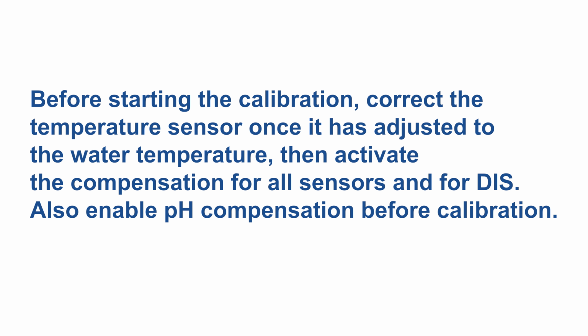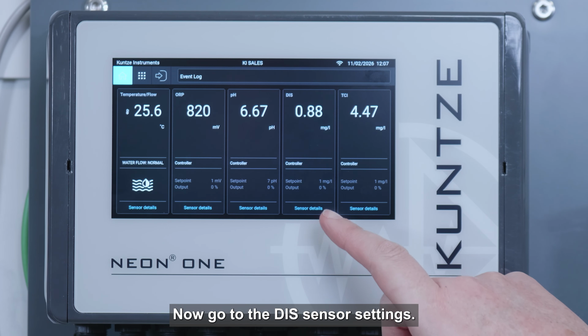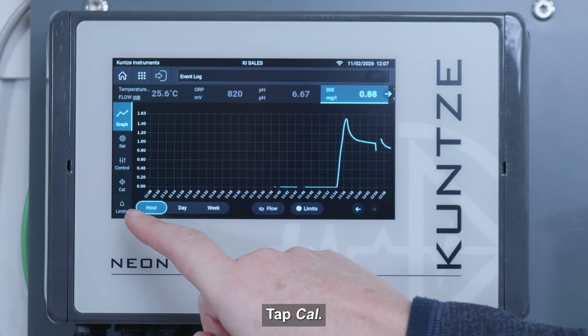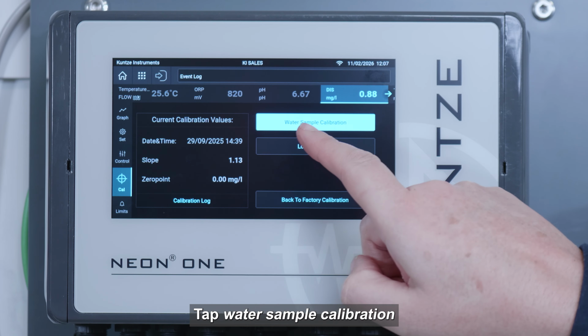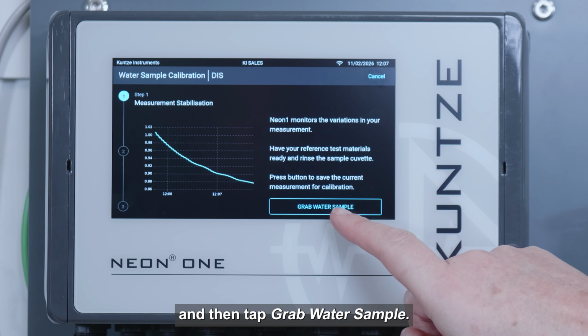minutes. DIS sensor calibration. Before starting the calibration, correct the temperature sensor once it has adjusted to the water temperature, then activate the compensation for all sensors and for DIS. Also enable pH compensation before calibration. Now go to the DIS sensor settings, tap Cal, tap Water Sample Calibration, and then tap Grab Water Sample.